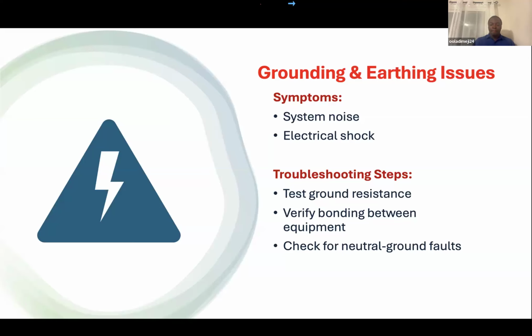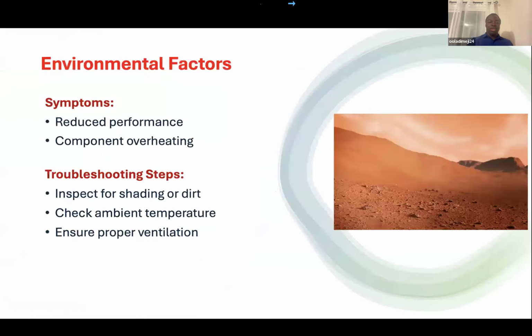Then check for neutral to ground faults to see if there is any leakage. Then you have environmental factors as well. They reduce the performance of the system. That's component overheating, in the case of dust, in the case of hot weather. For example, during the Harmattan season, that's when you hear most clients say, "Oh, this system is not lasting as it used to be. We shut down before daybreak." And these are because of the environmental factors.